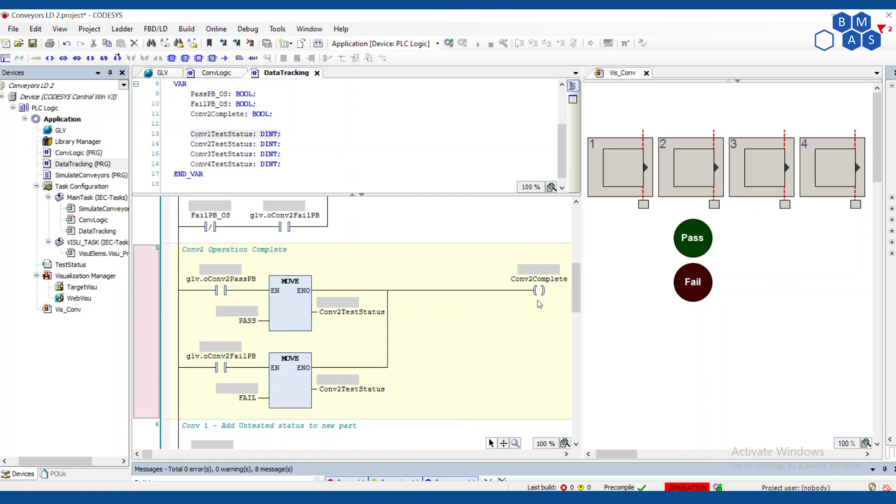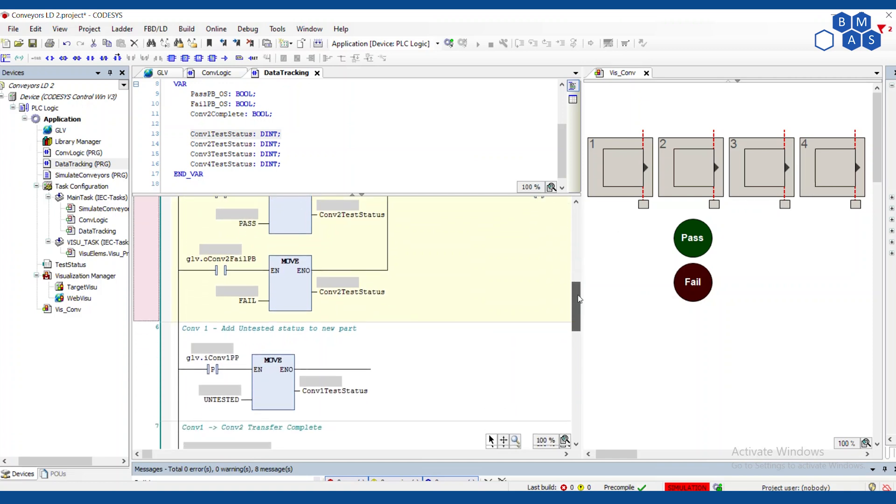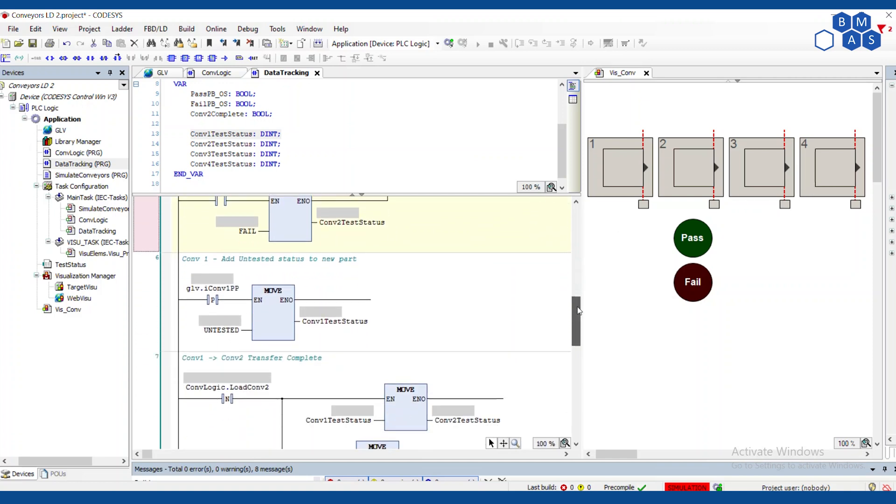If the fail light is on same thing, we move fail into conveyor two test status, we mark it complete. And if again, the operator changes their mind, they don't actually want to pass or fail it. They'll hit that button again, it'll turn off the light and then neither one of these branches is true. So the rung can't be true. Conveyor two won't be complete and the part cannot move forward.